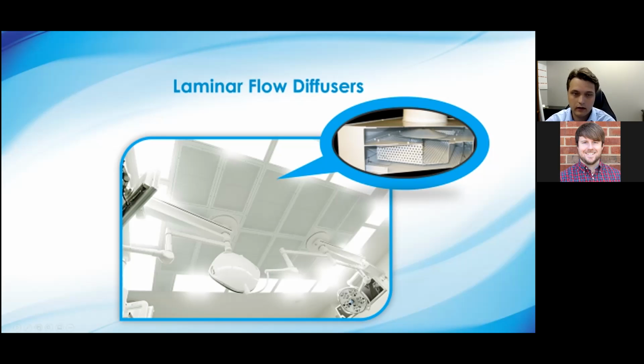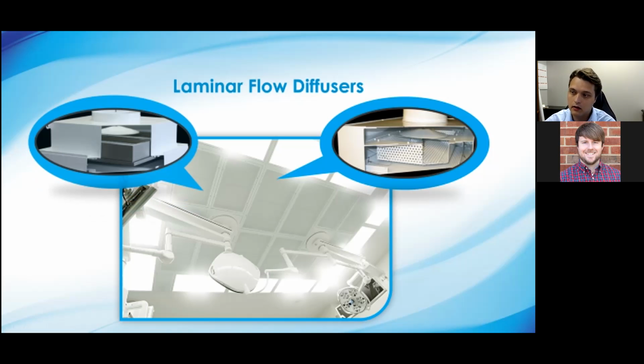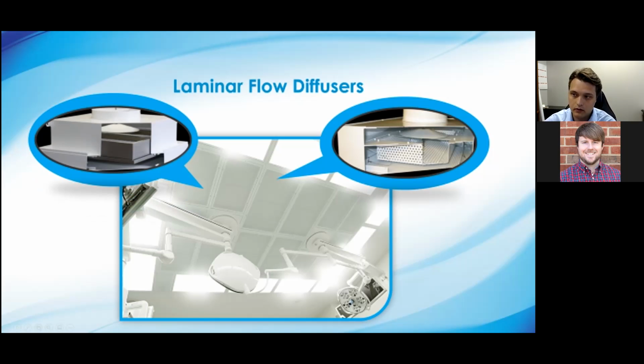One thing to keep in mind here is that a laminar flow diffuser is a passive device. It's taking whatever air you're giving it and just smoothing it out. That's the only role that most laminar flow diffuser systems play. They're not controlling the temperature, the velocity, any of those other properties of the air, just the flow right as it leaves its faceplate. You can accomplish the same thing with a HEPA diffuser. You just know that you now have a HEPA filter right in that diffuser, and now you're providing, for sure, as clean air as you can reasonably get directly over that patient, mitigating any risk of leakage in the ductwork leading from the air handler, where you otherwise could have a HEPA filter all the way to the room.